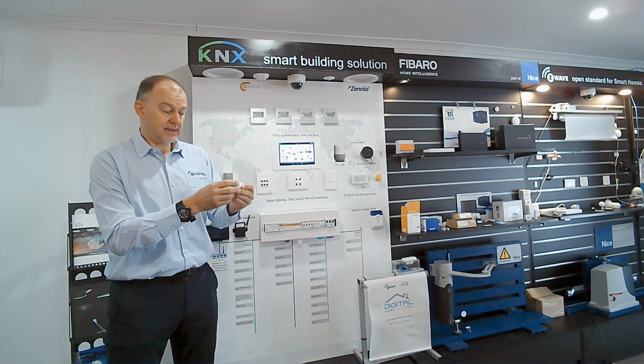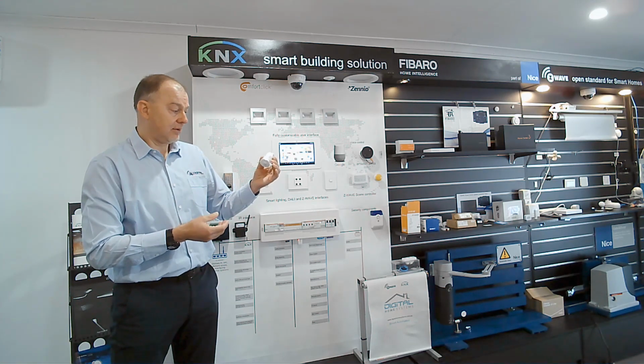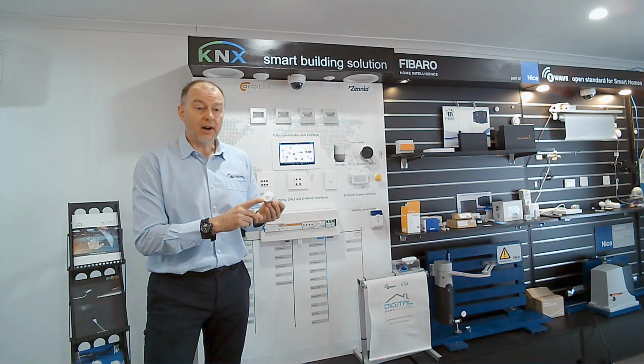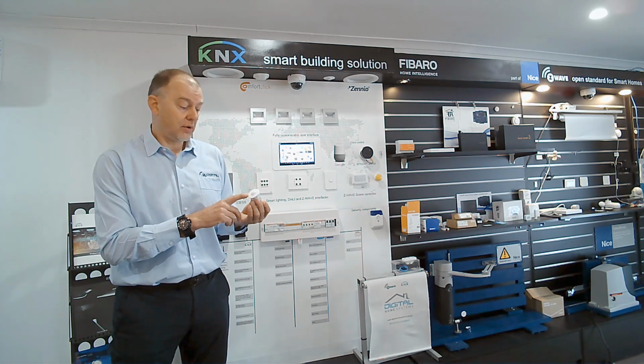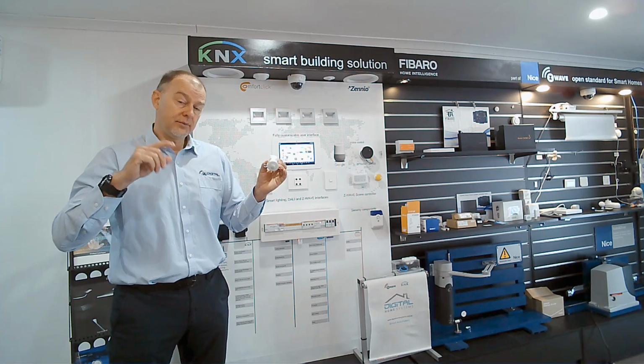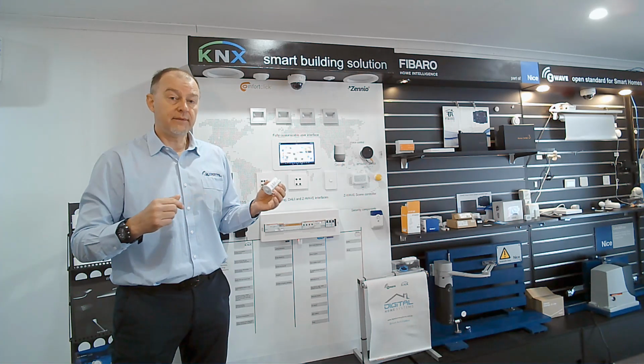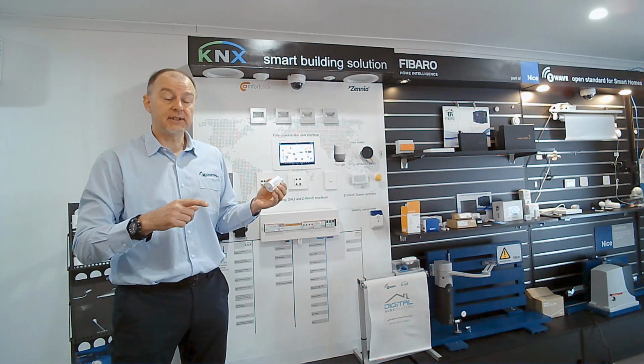So this is the device. It is nicely recessed in the ceiling with easy to install mounts. It's powered by KNX, 10 milliamps current. It is rated IP65, which is perfectly suitable for rooms where you may expect some moisture. This device is ideally installed on a ceiling from 2 to 5 meters high.